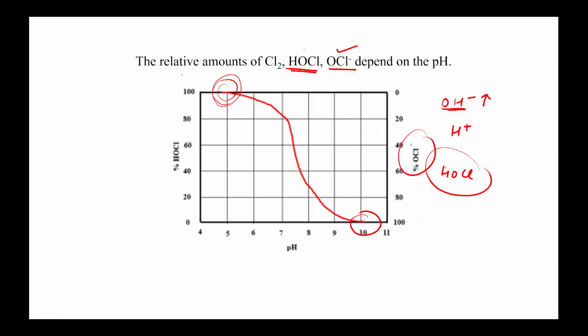When we add chlorine to water, it will react with the H plus ion of the water and form hypochlorous acid. But this reaction is pH dependent, because hypochlorous acid is basically an acid. If you remember from the first class, take the simple acid example HCl: if we put HCl in water, it will dissociate into H plus ion and Cl minus ion, right? Similarly, hypochlorous acid can also dissociate into H plus ions and OCl minus ions. But this dissociation is dependent on pH.